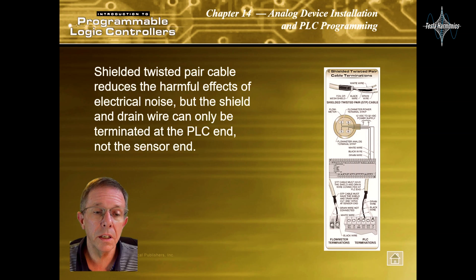Shielded twisted pair cable reduces the harmful effects of electrical noise, but the shield and drain wire can only be terminated at the PLC end, not the sensor end.